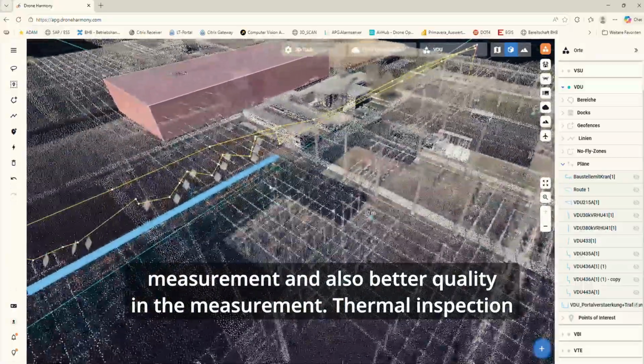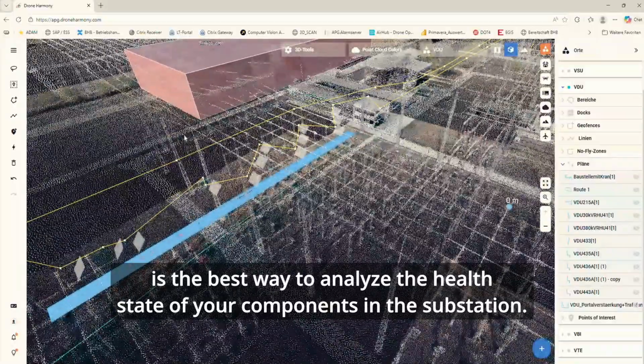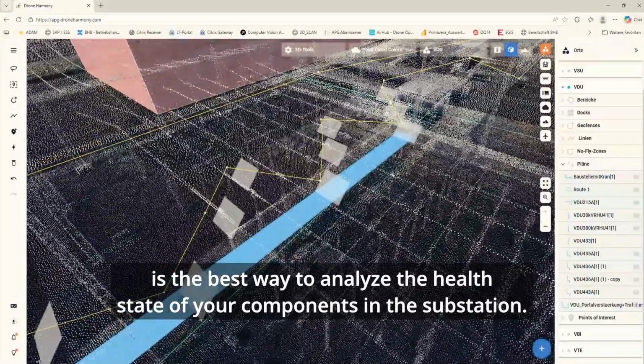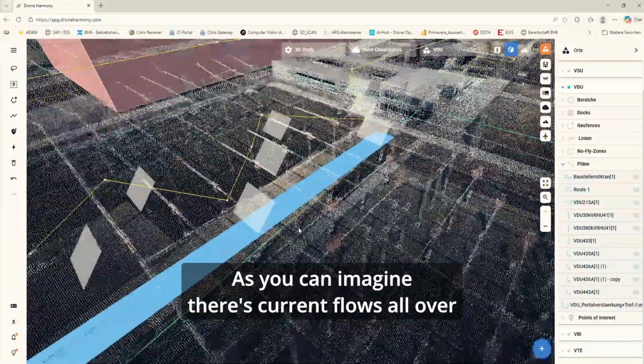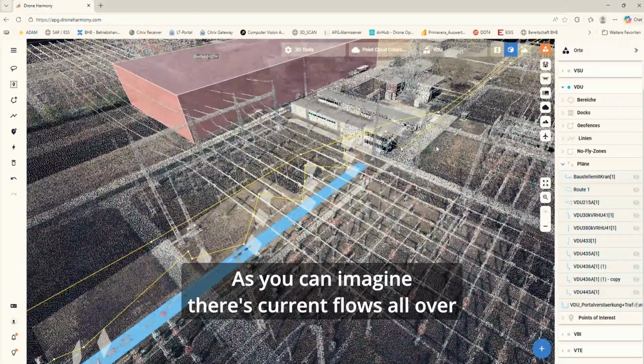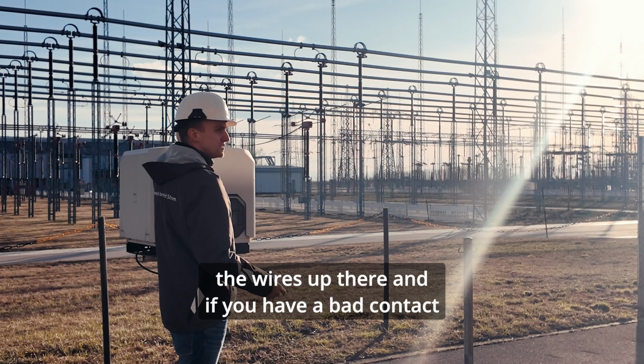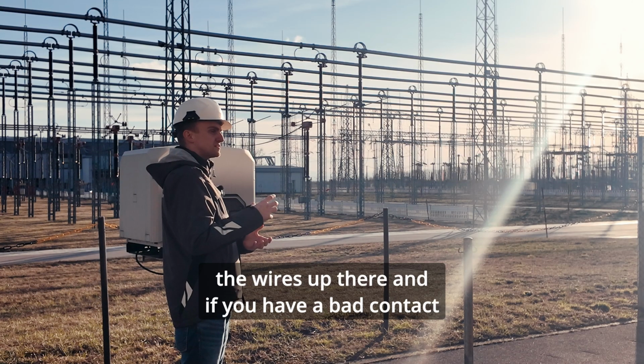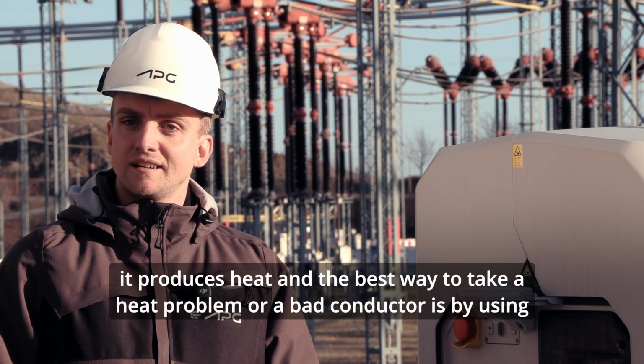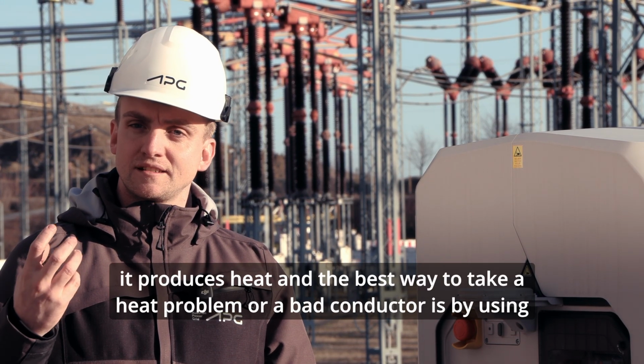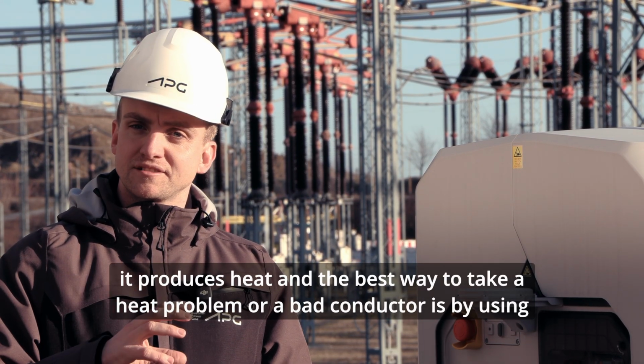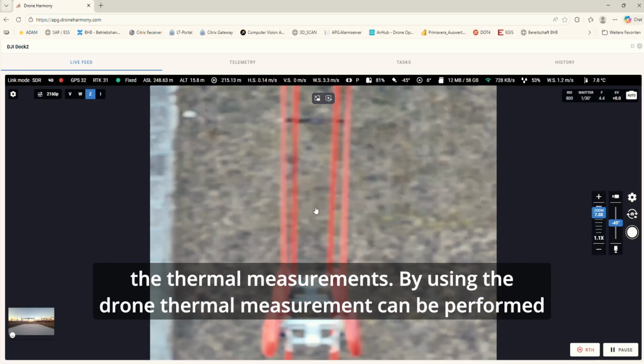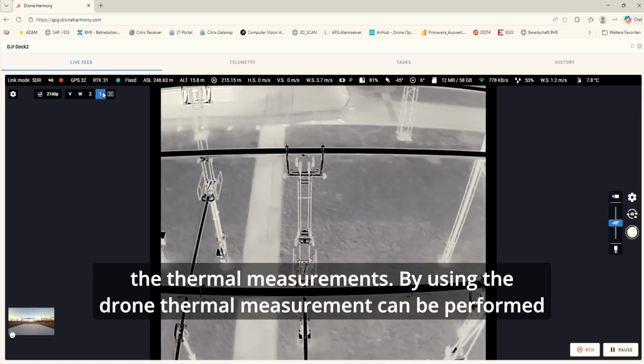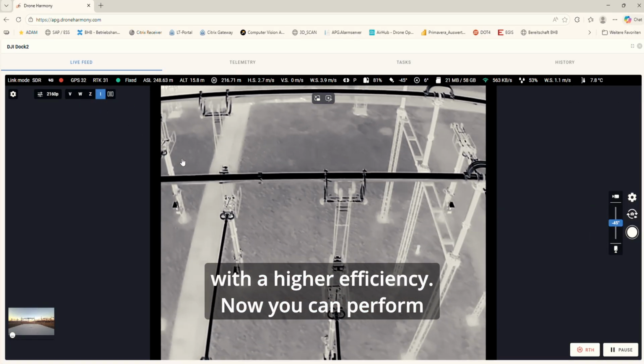Thermal inspection is the best way to analyze the health state of your components in the substation. As you can imagine, current flows all over the wires up there, and if you have a bad contact, it produces heat. The best way to detect a heat problem or a bad conductor is by using thermal measurement. So by using the drone, thermal measurement can be performed with higher efficiency.